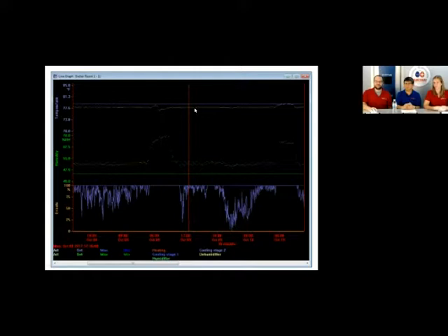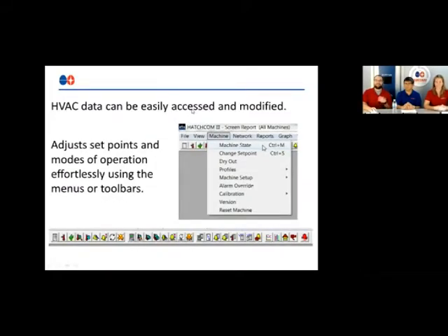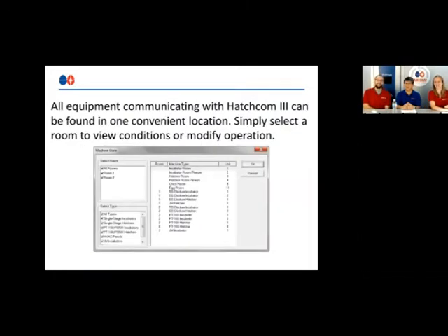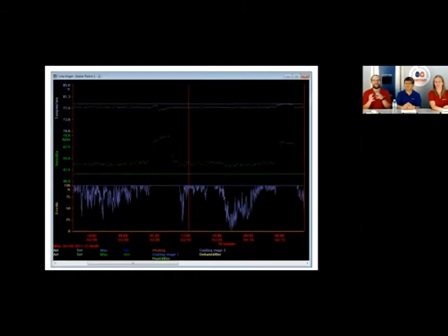Each little dot is a 5-minute increment. So if you were to double click, what it does is it shows all the pertinent information to that dot down in the bottom, so you can see if heating or cooling was on, what the temperature was, and the min and max temperatures in those ranges. It's also useful for just diagnosing why heating or cooling didn't come on.